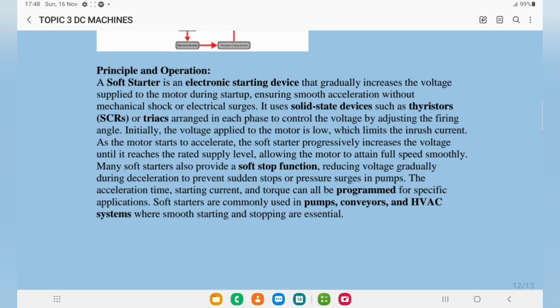Initially, the voltage applied to the motor is always low, which limits the inrush current. As the motor starts to accelerate, the soft starter progressively increases the voltage until it reaches the rated supply level, allowing the motor to attain full speed smoothly.